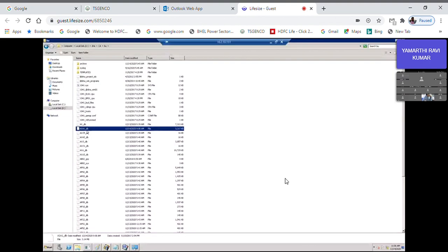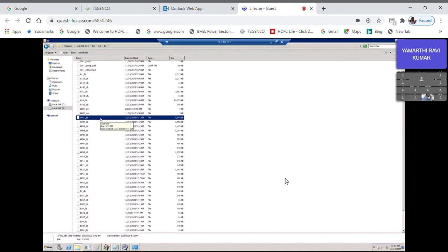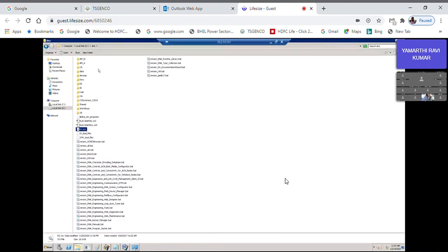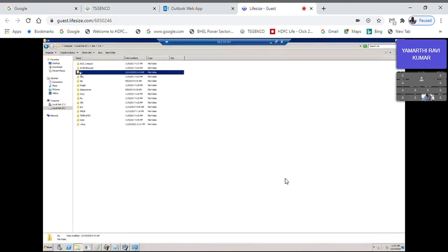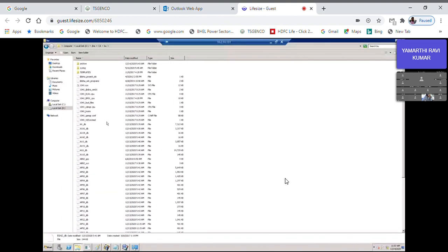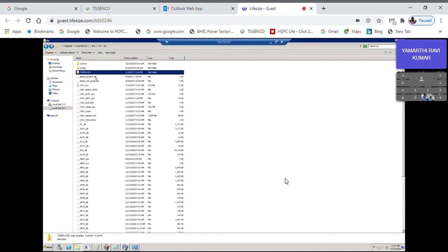Now the ACN may be getting all the general Linux-based files for booting. Project-specific files, it will take from BU. All those files are present here. For any Windows-based node, we put the system file under DNA. But in case of ACN, we have to load all the system files under this particular location. All the files related to AP01, AP02, or all the ACNs, the system files will be loaded here. Now I'll show a sample system file of ACN.